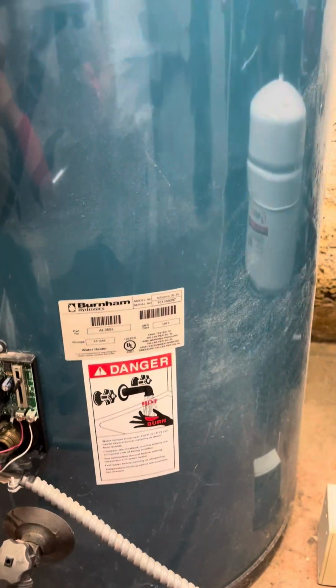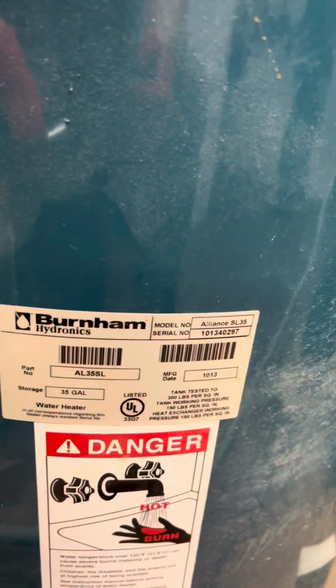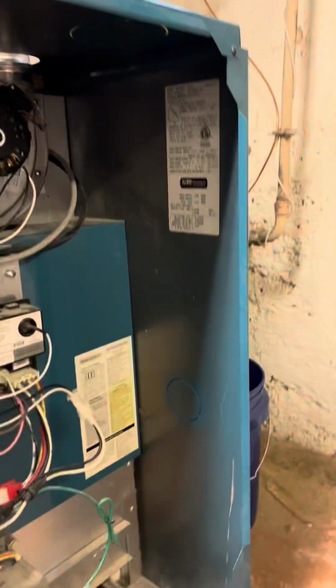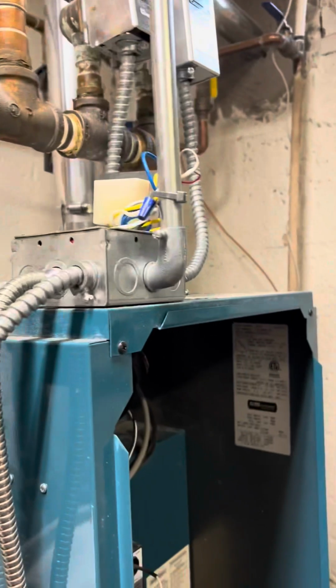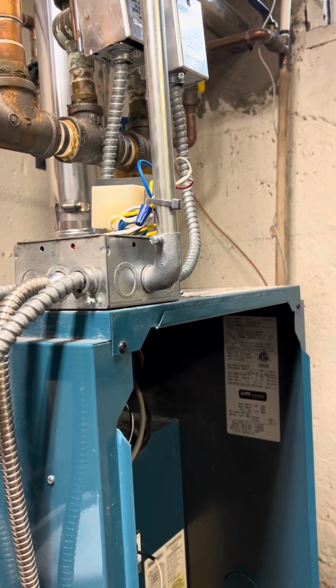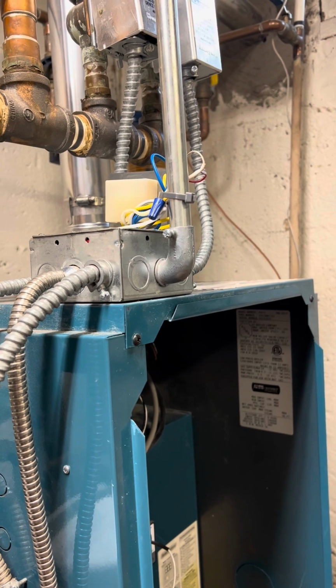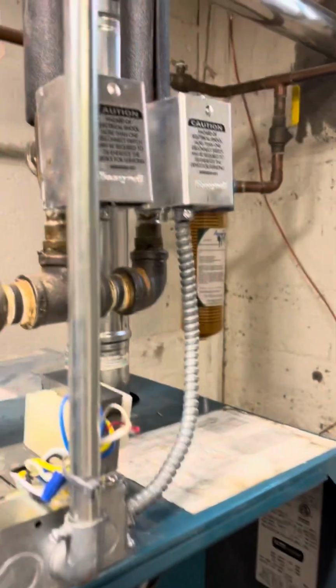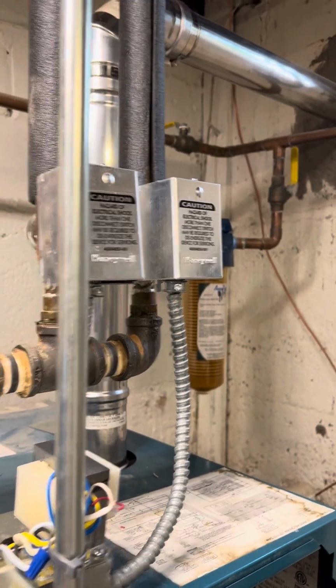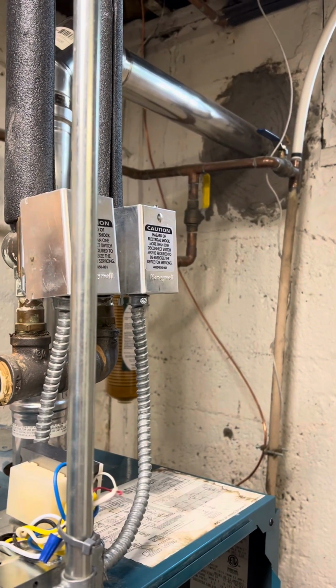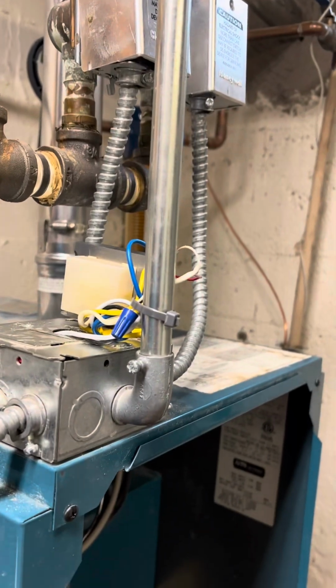So we're at a Burnham boiler job, and we had to do a lot of rewiring right over here. This transformer kept on popping. It had 9 amps on it, and that was due to a faulty zone valve. So the zone valve was creating too much amperage, taking out the transformer.